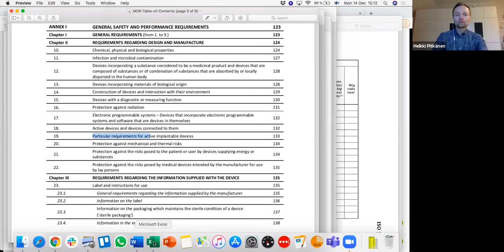So let me go directly to the table. This is about risk management, but this would be the general safety and performance requirements table, and the typical method of going through the requirements by the manufacturer. So if the notified body comes and assesses you, or if it's the authority, then they would expect to see this kind of a table where you have broken down the requirements into rows, and you can break them down even to smaller pieces if you like. But the point is that you will need to define whether this one requirement is applicable to your device or not. And if not, you would need to give a rationale on their non-applicability. And for example, the general requirements, they are applicable to every manufacturer. But for software, for example, there are plenty that don't apply.